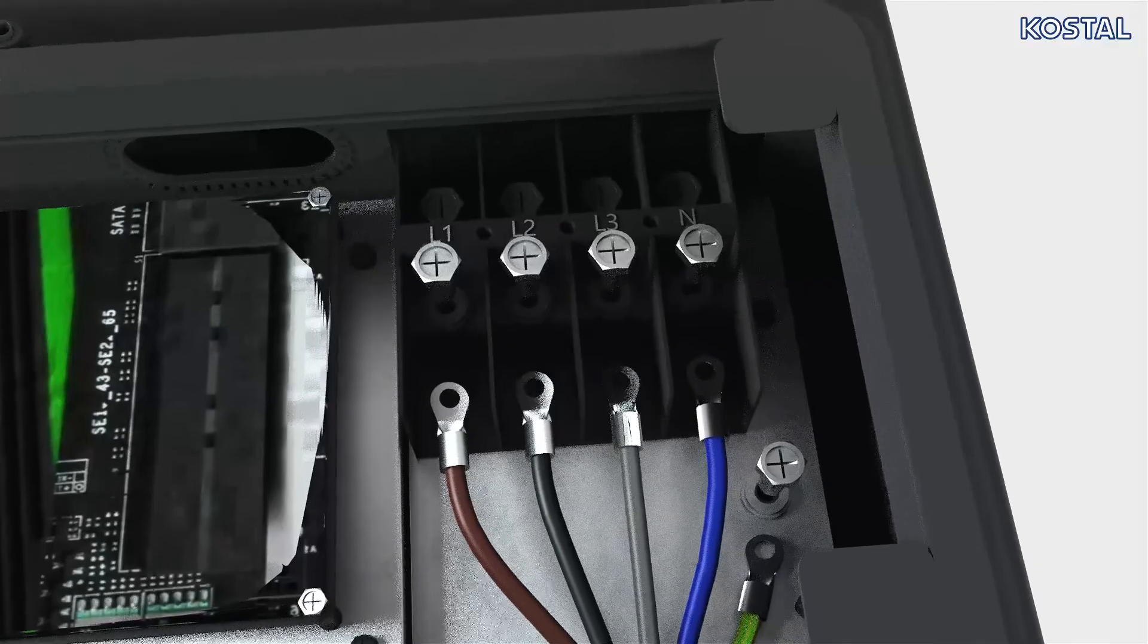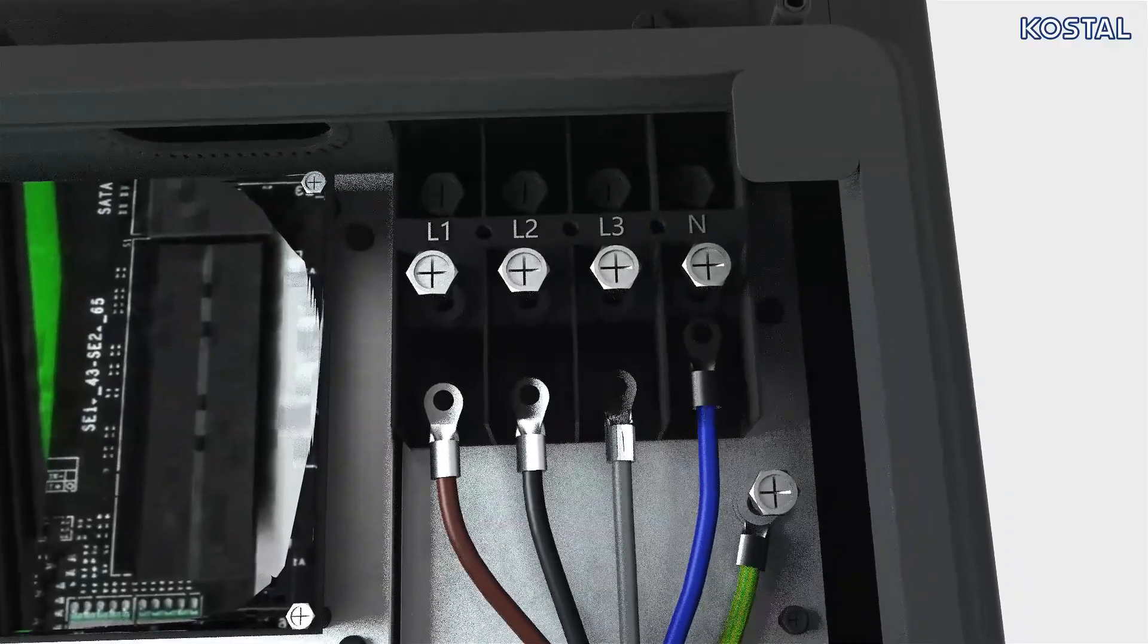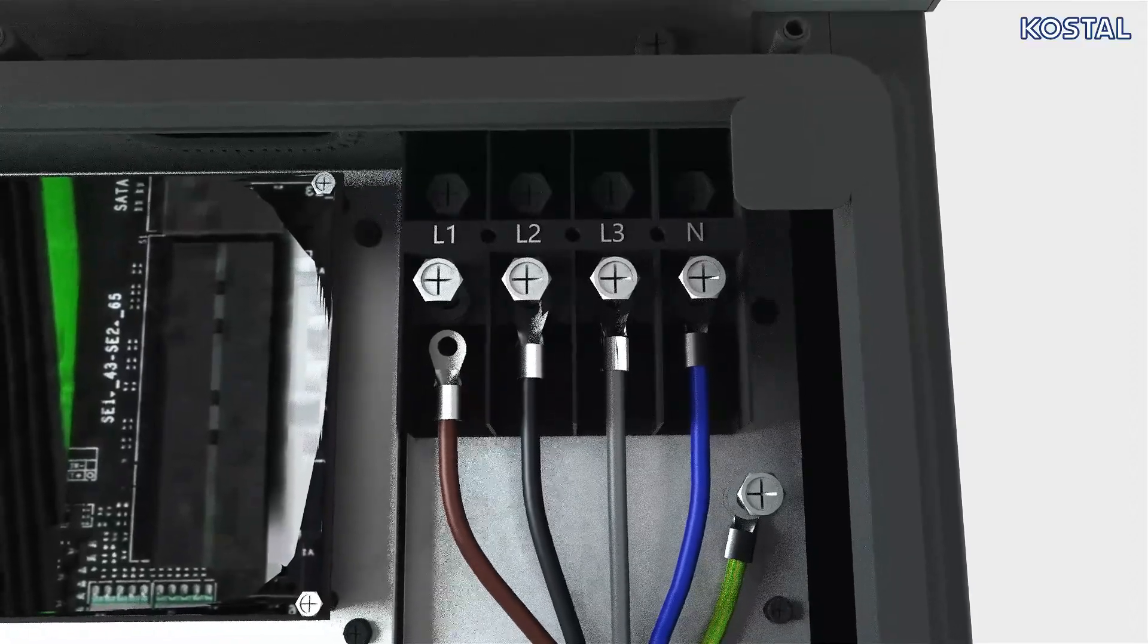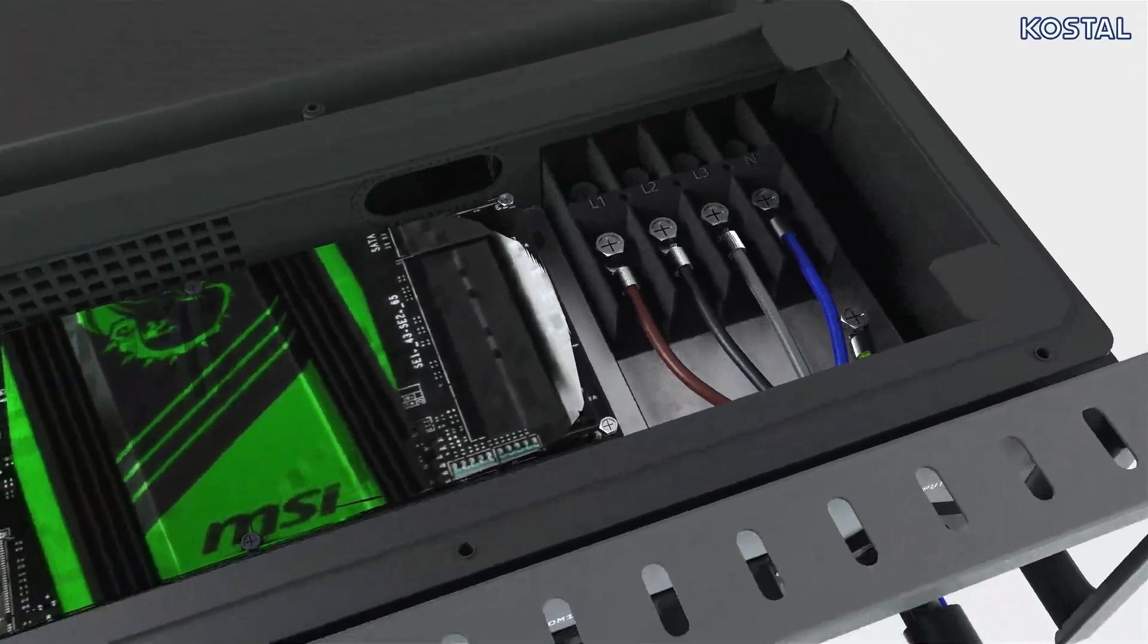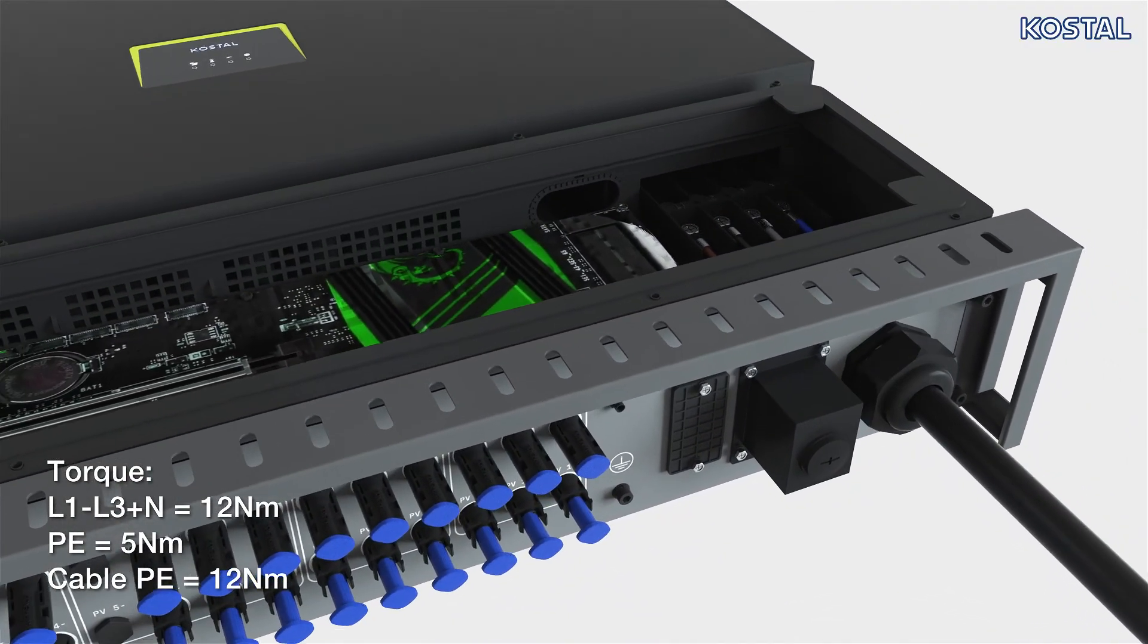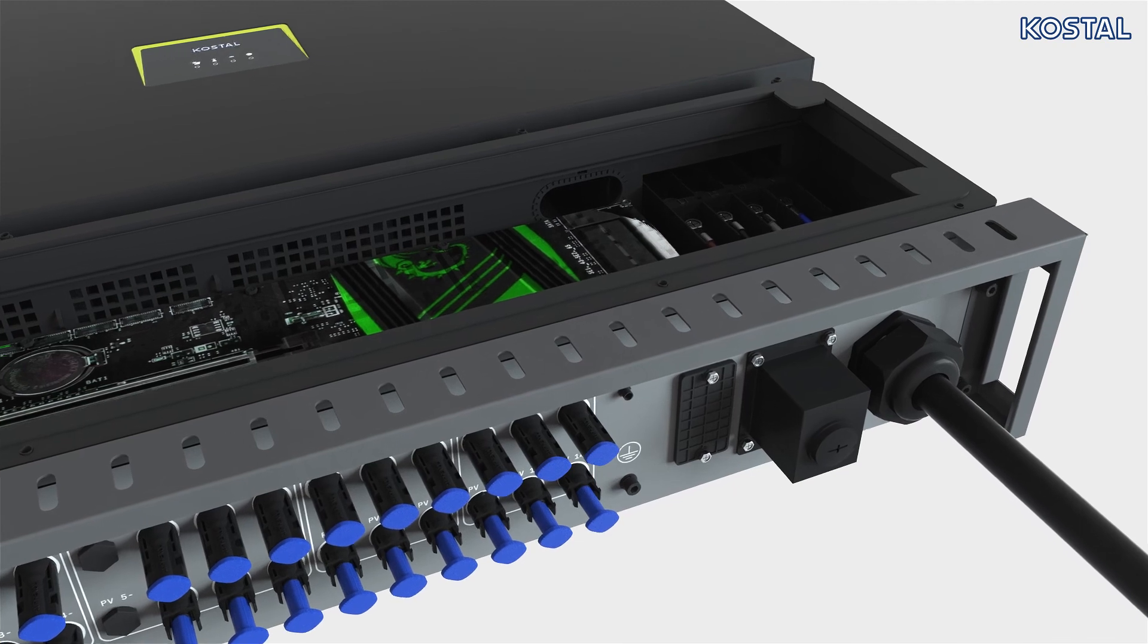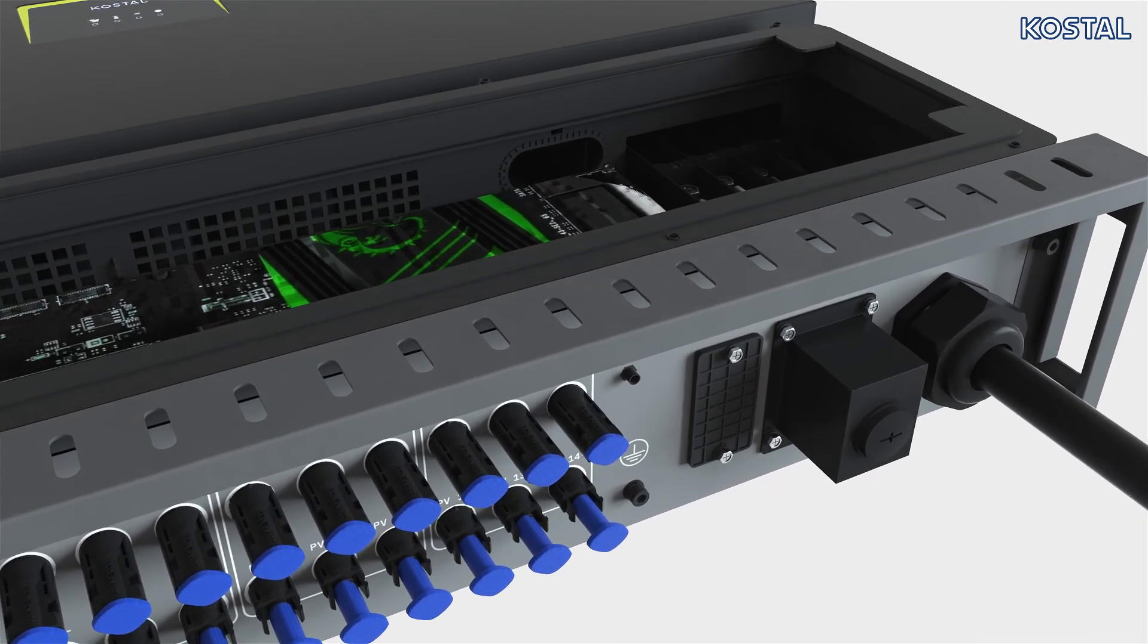Use ring cable lugs M8 to connect the wires to the AC connection terminal following the label. Start with the PE cable. Screw the sealing ring back down with the cable on the inverter. The AC cable is now connected and can be properly laid in the sub-distribution. Close the terminal compartment's housing cover and screw it tight.